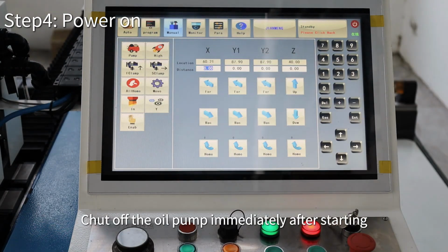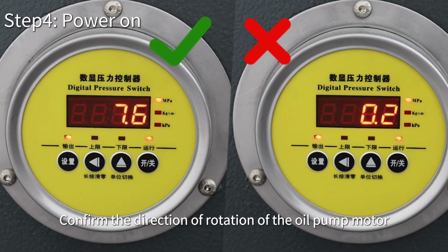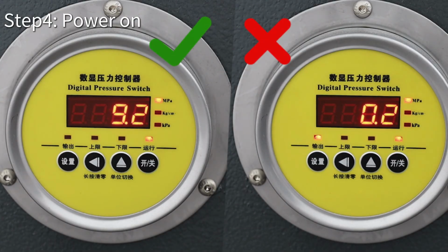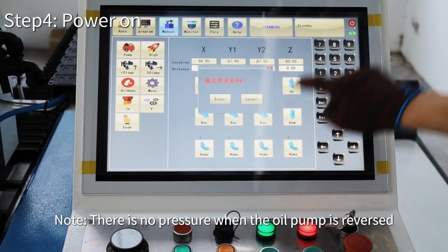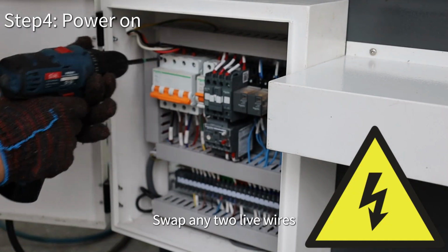Shut off the oil pump immediately after starting, and confirm the direction of rotation of the oil pump motor. Note, there is no pressure when the oil pump is reversed. If the oil gauge value does not rise, shut down the power and swap any 2 live wires.